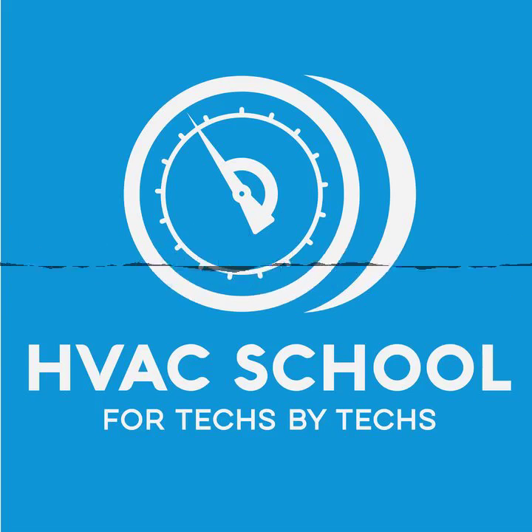Getting delivered capacity is huge. You can actually show your customer right there on your phone, look, this is how much capacity this system is delivering, here's what you paid for, here's what you got. It's also a great way to get your indoor wet bulb and dry bulb, which you need anyway to calculate superheat on a fixed orifice system, or target delta T and air temperature split. It's just a good all-around temperature measurement device, plus it gives you data you can only get from a thermohygrometer, with the ability to get it in the duct.